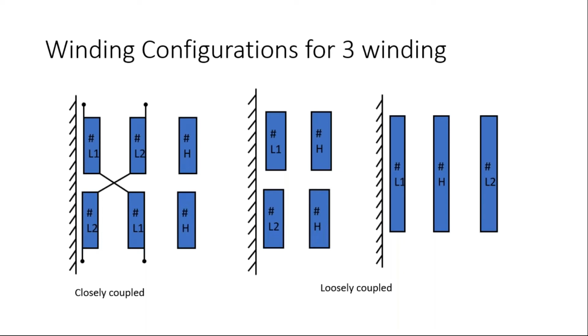The other two configurations, which are more common and closer to the standard configuration of transformers, have the LVs closer to the core and the HVs outside. It has fewer limitations in bringing HV taps out, but these transformers also have a high current on the LV, so it becomes equally difficult to bring those LV leads out. And the first one, closely coupled, is probably the most difficult one manufacturing wise, because you start one of the windings, then you wind the second one, and then you take it to the second layer and have a crisscross connection made in between.